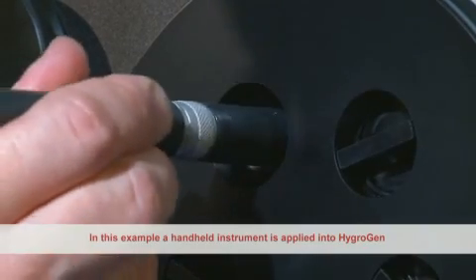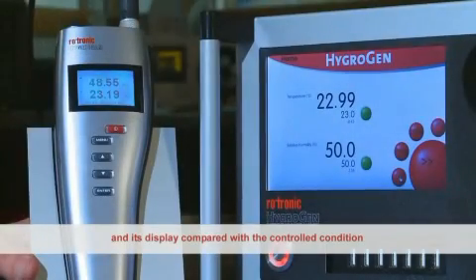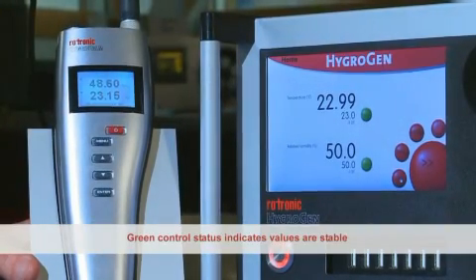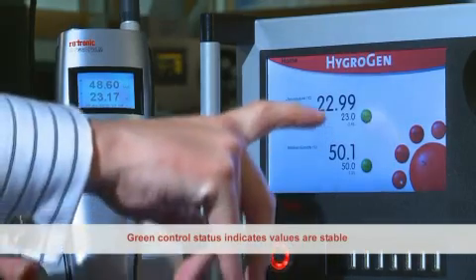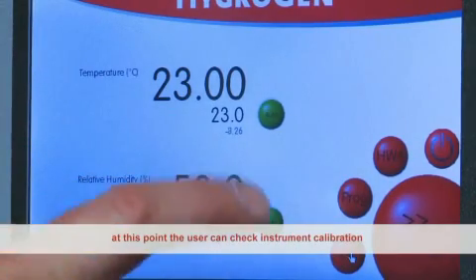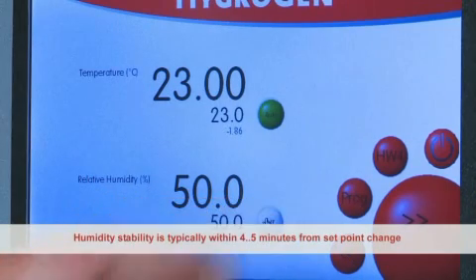In this example, a handheld instrument is applied into the HygroGen and is its display compared with the controlled condition. Green control status indicates values are stable, at which point the user can check instrument calibration.